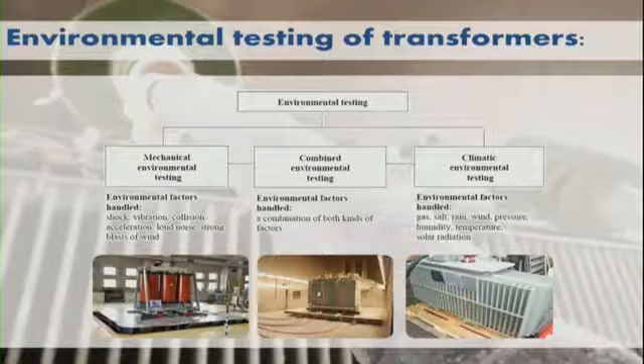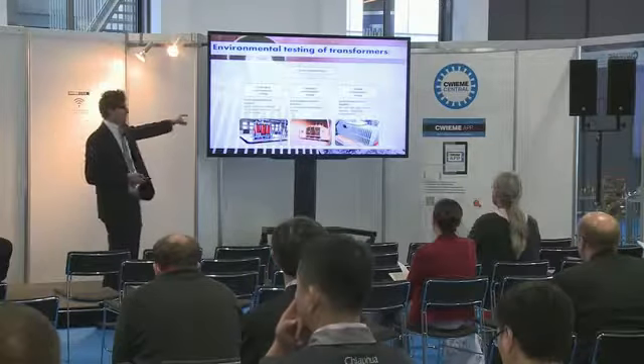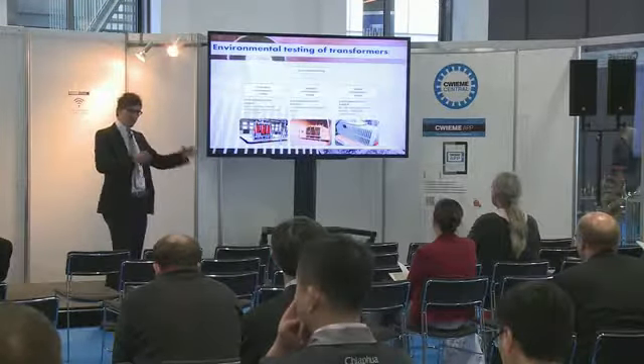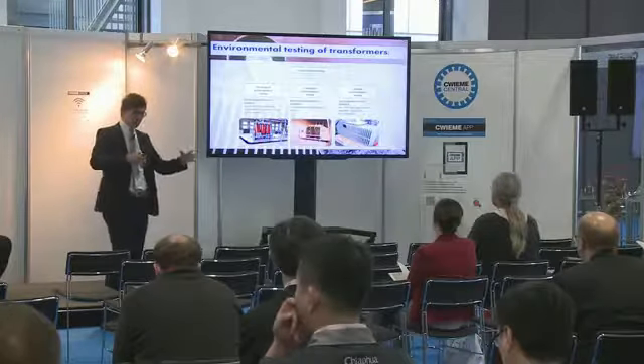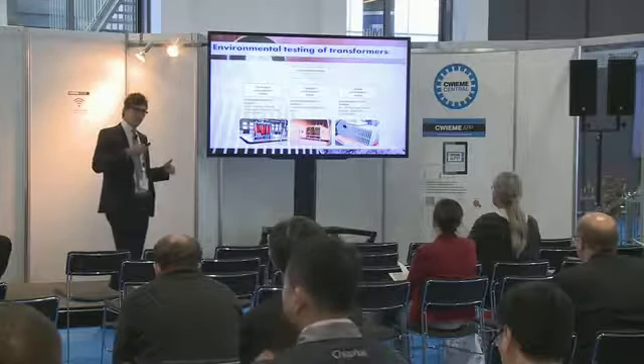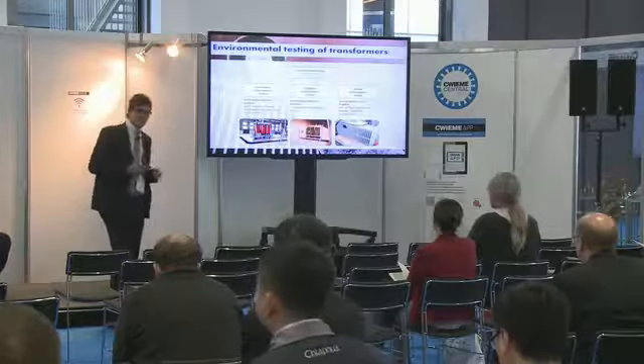Testing. Environmental testing. On one hand, you can just do the climatic testing, for example for corrosion. On the right-hand side, you can only do the vibrations on a vibration table. It would be better if we combine them. What we do, for example, in our laboratory, is place a wind turbine transformer inside the climate chamber. We cool it down to a very low temperature, minus 30, for example. And then we put full load on the transformer. In the case of a liquid filled transformer, we have a pressure increase then, so extra stresses on the tank, and in that way we can check if any leakage will occur or not.